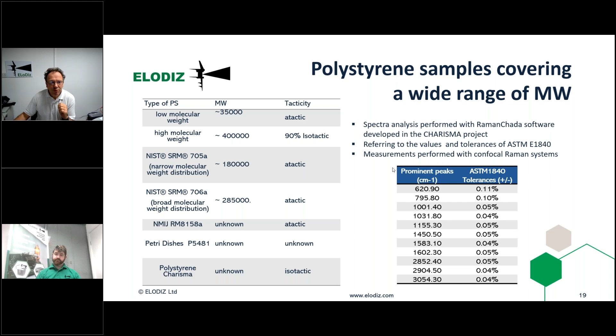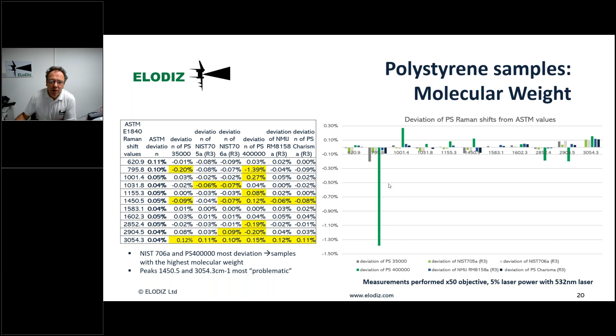There are some deviations that are quite important, and some instruments behave well, while others behave really badly. So it is important to take the right polystyrene. We have analyzed, I think, in total about 15 different types of polystyrene, and we have focused our attention only on 3 or 4 that are fully traceable and have good reproducibility on the system across the full broad number of instruments of the consortium. And we have analyzed very carefully what the polystyrene effect is. Because polystyrene is one of the most used reference samples, we have analyzed the measured values, the ASTM values, and the samples that we can obtain with our systems, and then we have created new tables that are going to be proposed to the ASTM and ISO organizations to reevaluate the tables on peak positions for polystyrene.